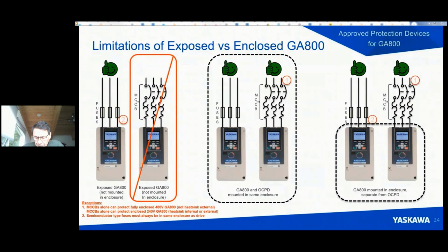However, there is an exception, and as I mentioned before, if we look at item number 2 there, when the fuses are actually semiconductor type, then they must actually be in the same enclosure. Okay? And the other thing that I had mentioned before is Yaskawa's position is that when a circuit breaker is protecting the drive, we want to see not only the drive, but the entire drive, including its backside, in the same enclosure if it has capacitors on the backside. Okay, so those are some exceptions.